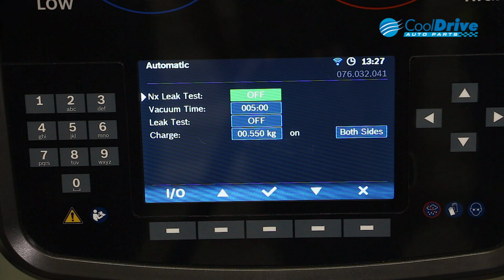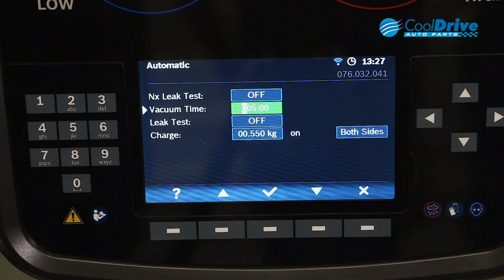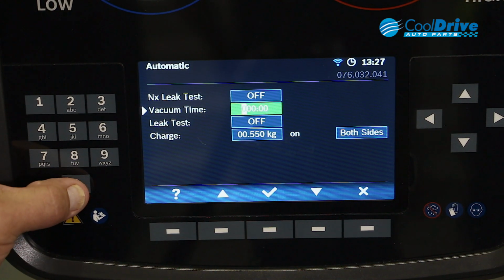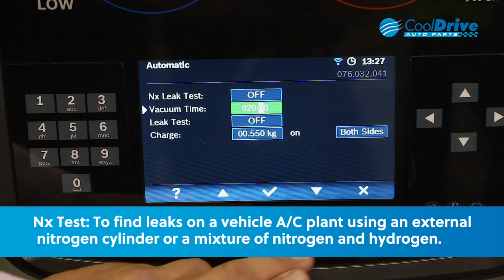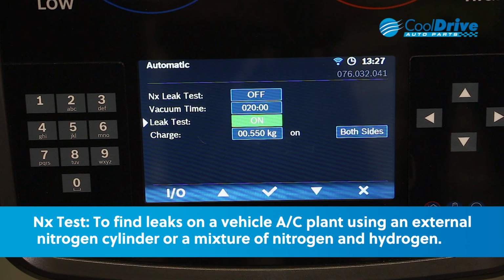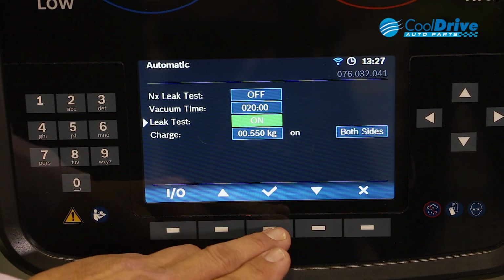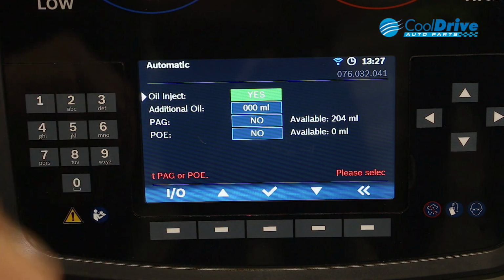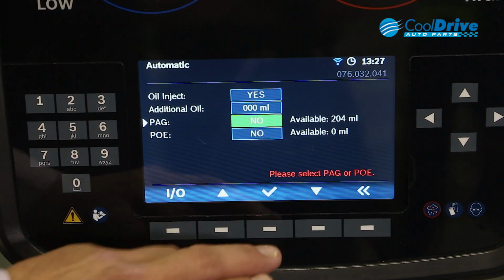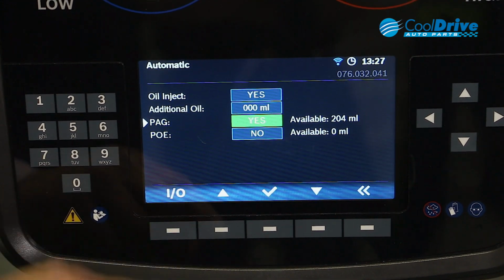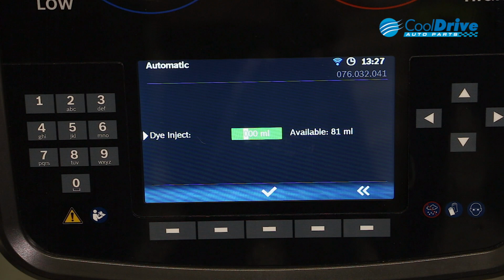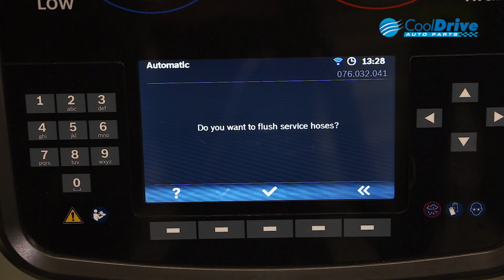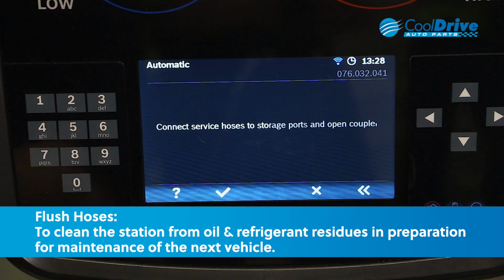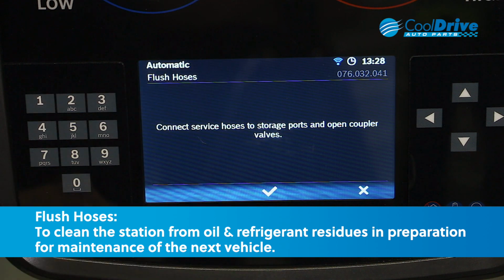We can add or continue. Takes us through our sub-menu again, so we will go through and we'll change our vacuum time through to 20 minutes. Our leak test will perform and our charge is set, and we will charge through both sides. Oil inject, yes. Additional oil, no. Yes, it is PAG. And in this case, we're going to inject 3 mil of dye. Do you want to flush the service hoses? Yes. Connect the service hoses to the storage ports and open the coupler valves.